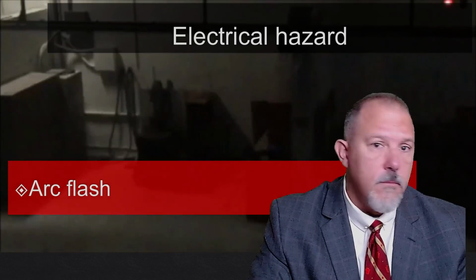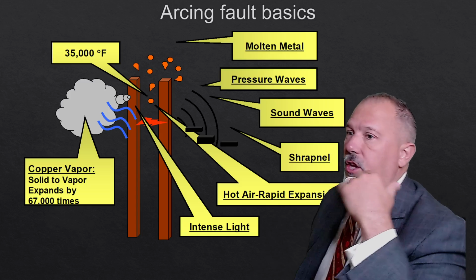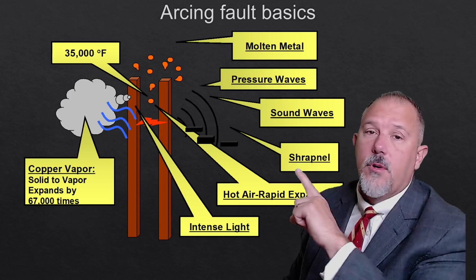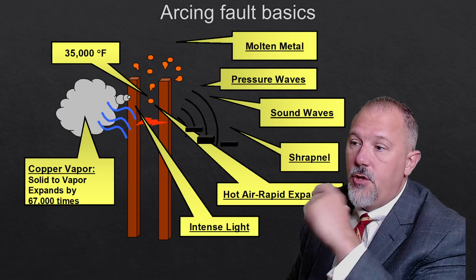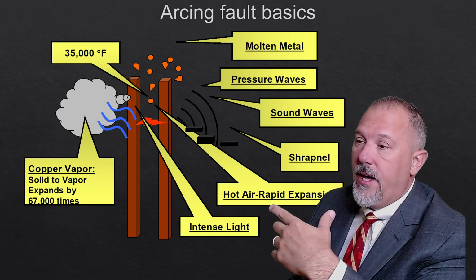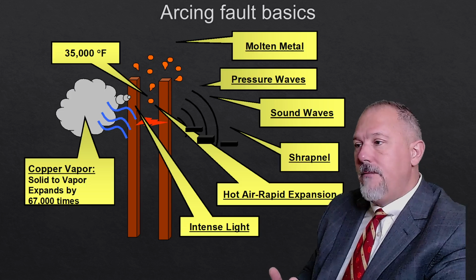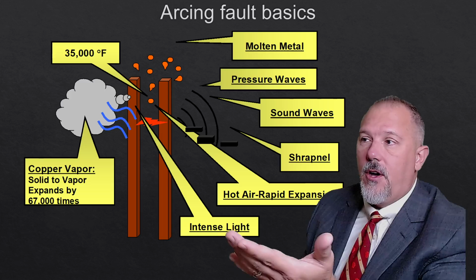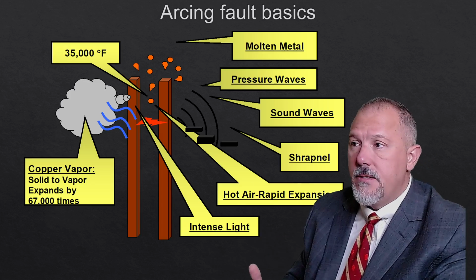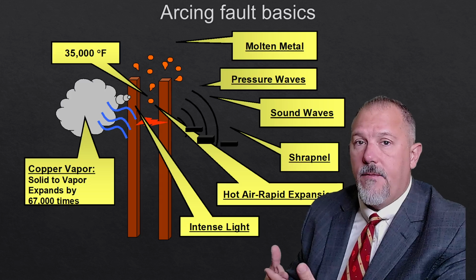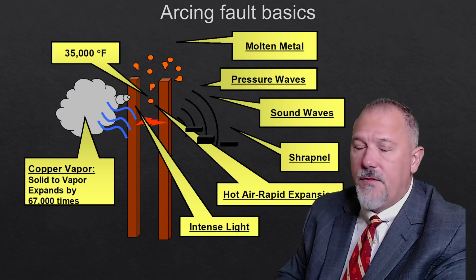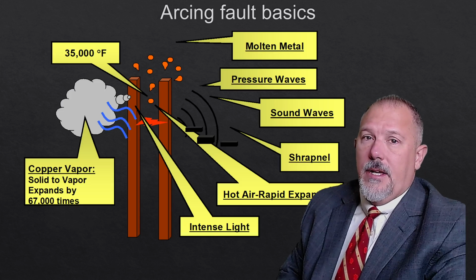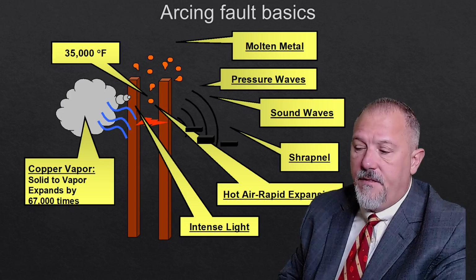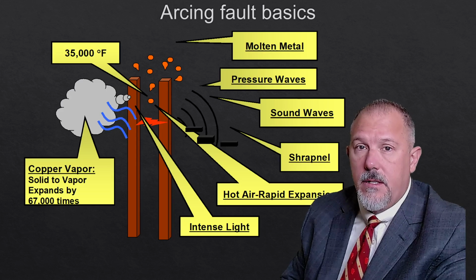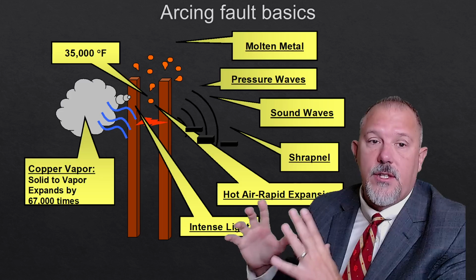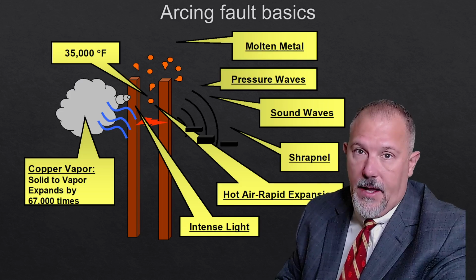Now, when you have an arc flash event, you've got a very high temperature, upwards of 35,000 degrees Fahrenheit. You have an intense light, as we saw. You have the hot air rapid expansion. You have molten metal that becomes vaporized. You've got a pressure wave, and we saw that with that glass that was vibrating. Obviously, you've got the sound and the light. It's a very intense event on many levels, as this image tries to convey.